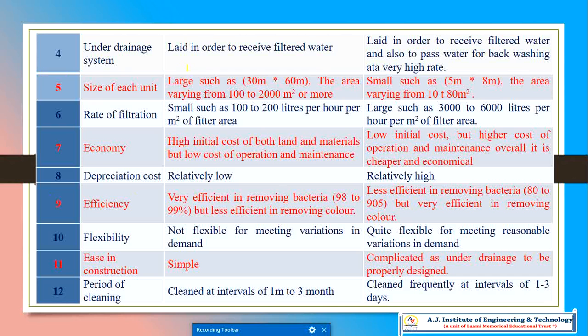The fourth comparison is the underdrain system. In the slow sand filter, the underdrain system is only laid in order to receive filtered water. But in the case of the rapid sand filter, it also passes water for back washing, so the underdrain system is also designed for back washing purposes.